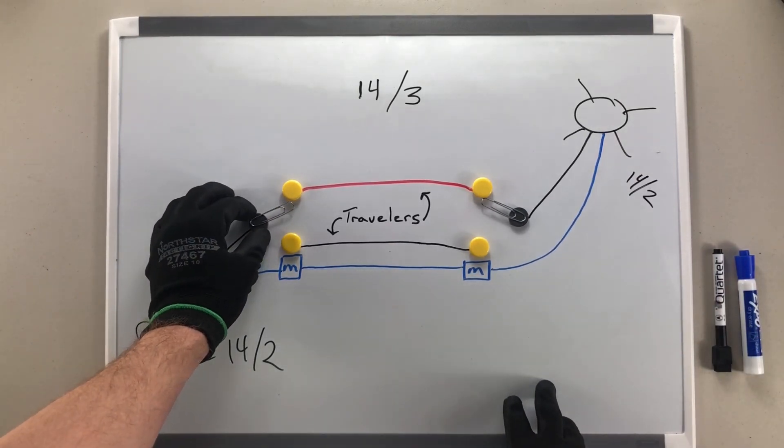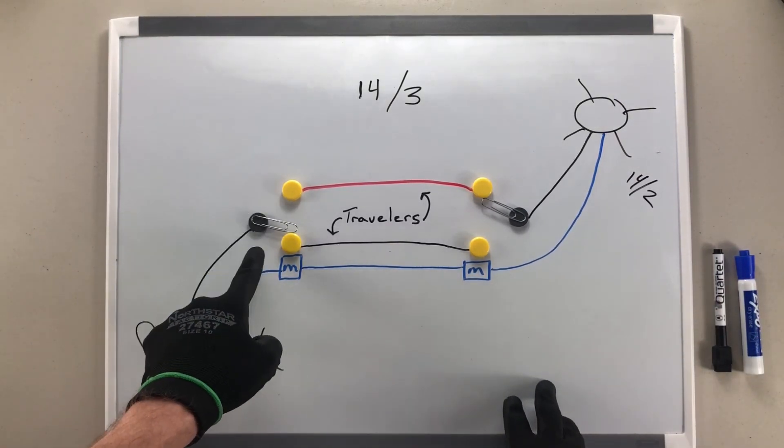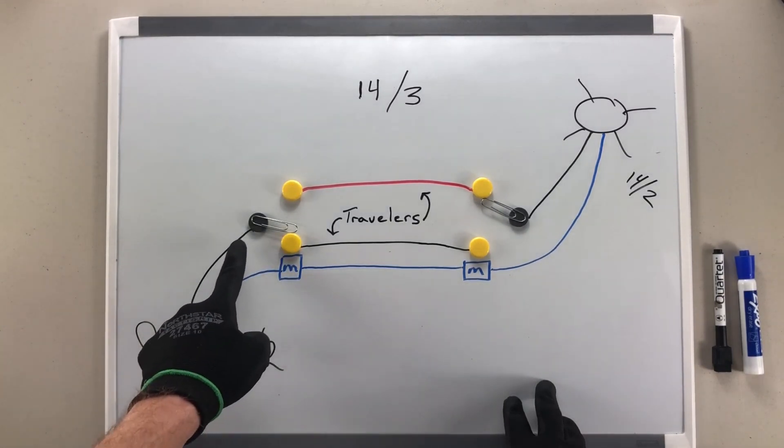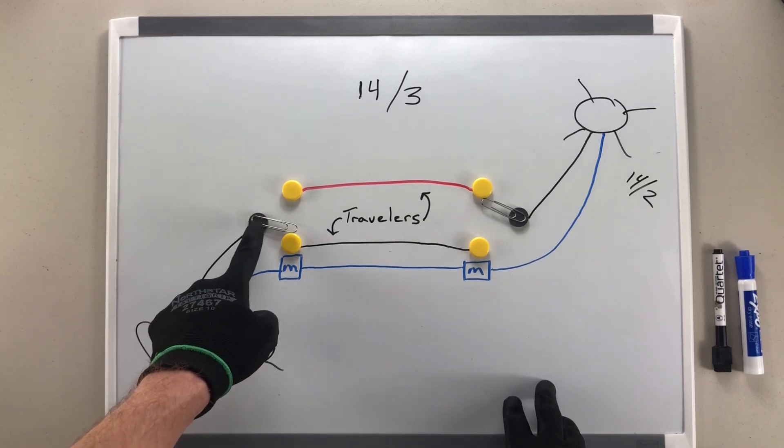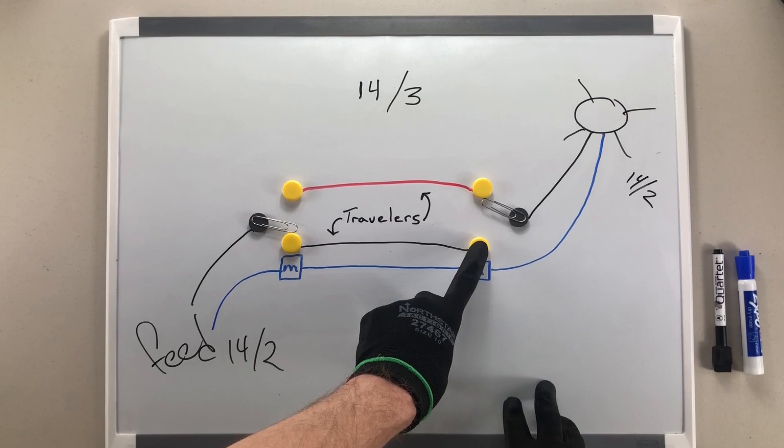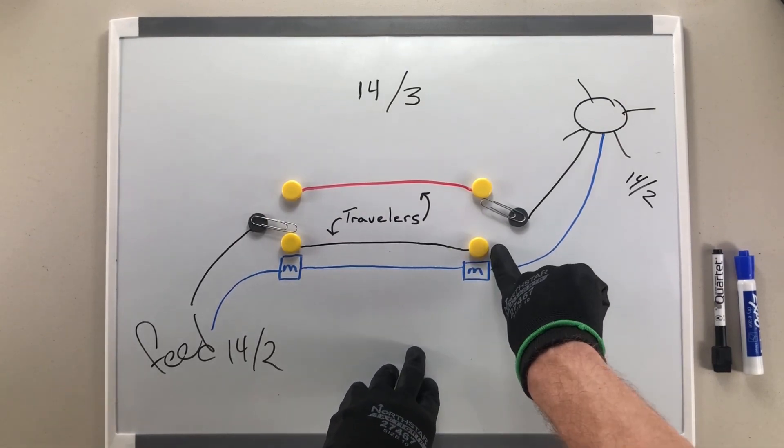Anytime we hit one of our three-way switches, it changes the condition of our common screw connection. Our power is now coming in across our common screw to this traveler, across, and the light is in an off condition because the power stops right here.